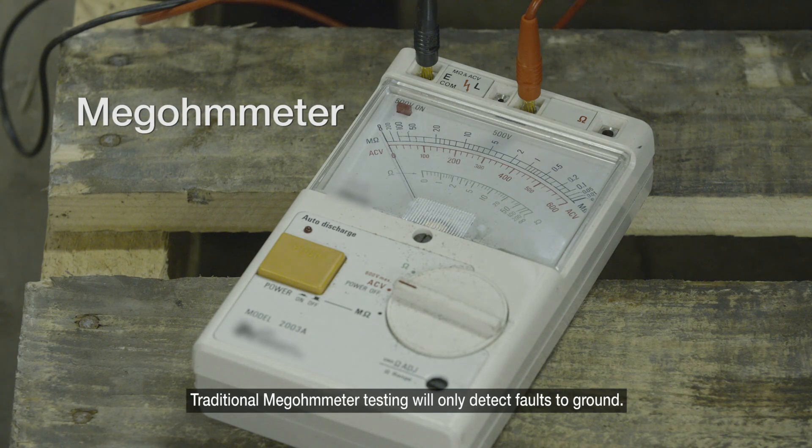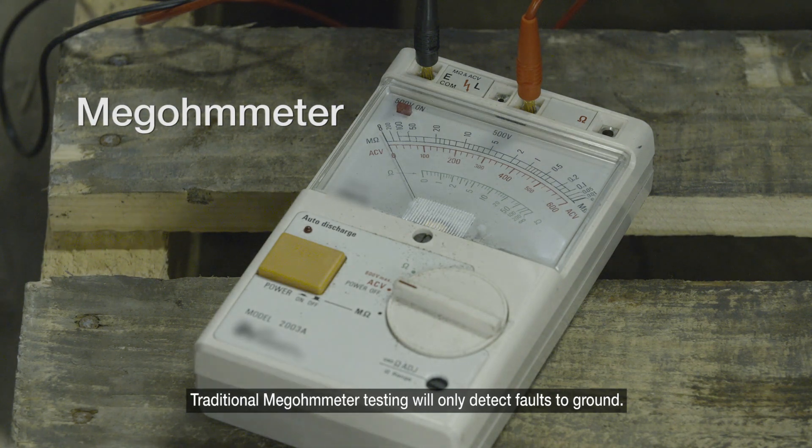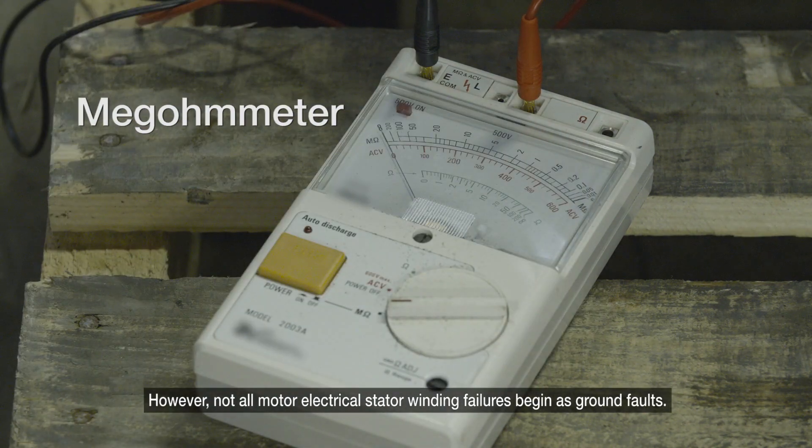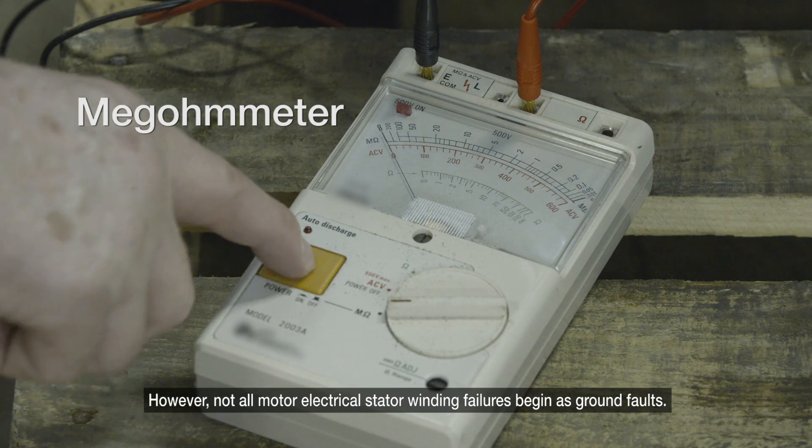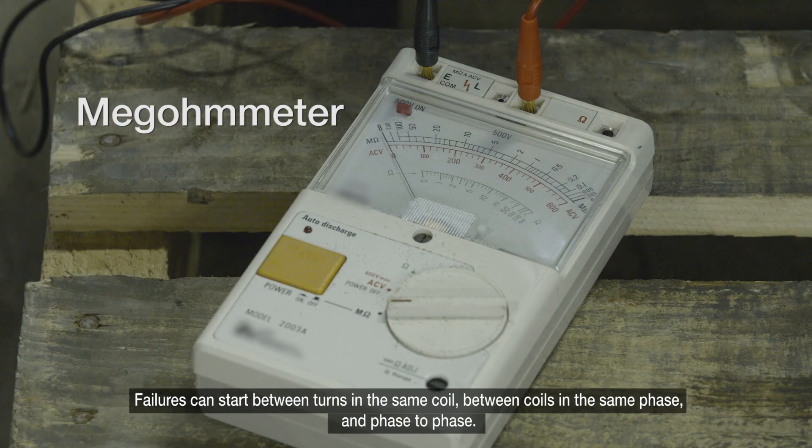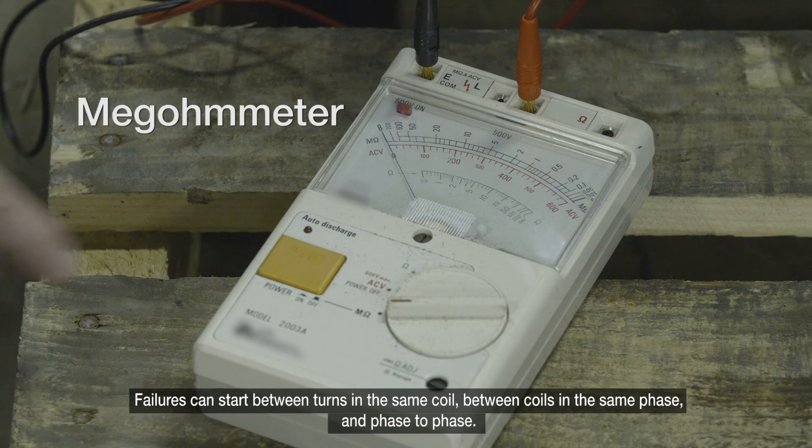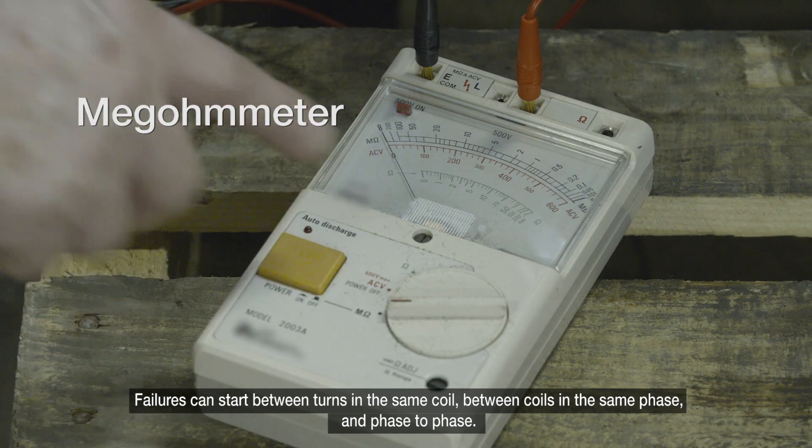Traditional megohmmeter testing will only detect faults to ground. However, not all motor electrical stator winding failures begin as ground faults. Failures can also start between turns in the same coil, between coils in the same phase, and phase to phase.